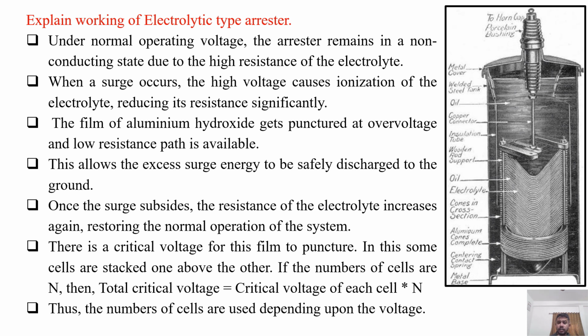Once the surge has subsided, the resistance of the electrolyte increases again, restoring the normal operation of the system and the high value of the resistance. There is a critical voltage for the film to puncture. In this, some cells are stacked one above the other. If the number of cells is n, then the total critical voltage is equal to the critical voltage of each cell multiplied by the number of cells, that is n. Thus, the number of cells used depends upon the voltage. When the voltage increases, the number of cells must be increased accordingly. So this is how the electrolytic type arrestor works.